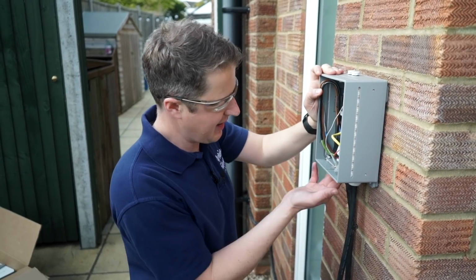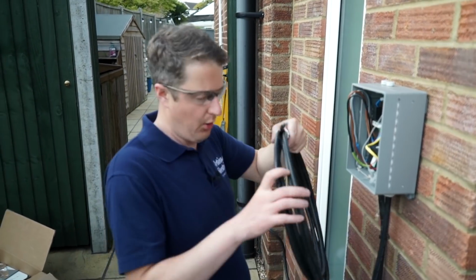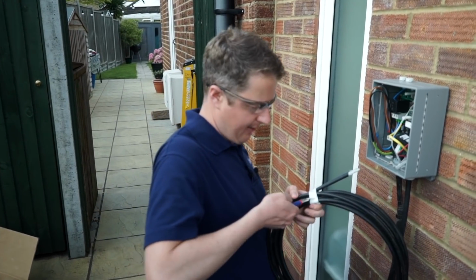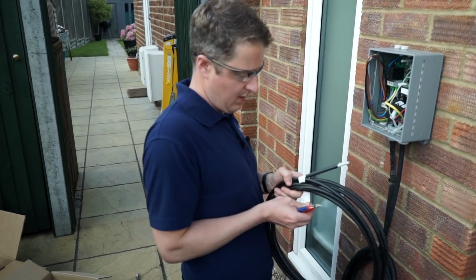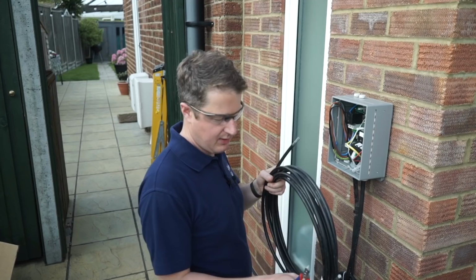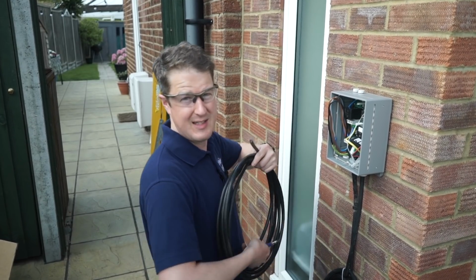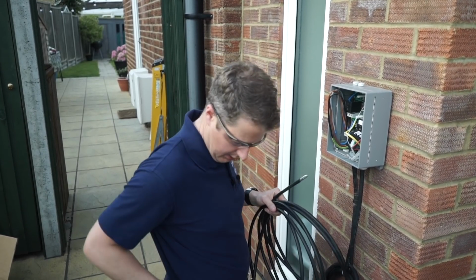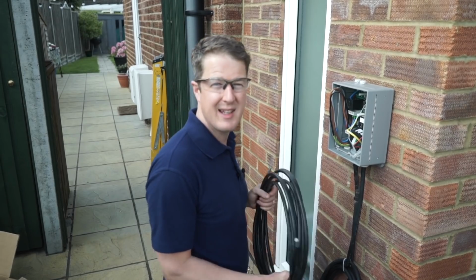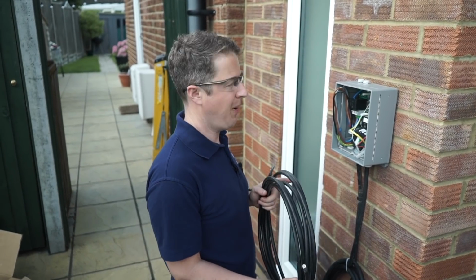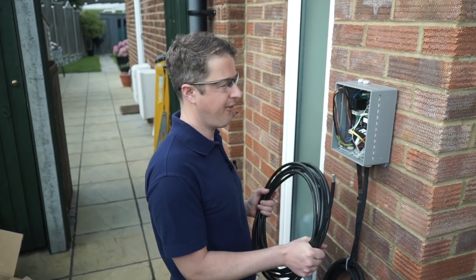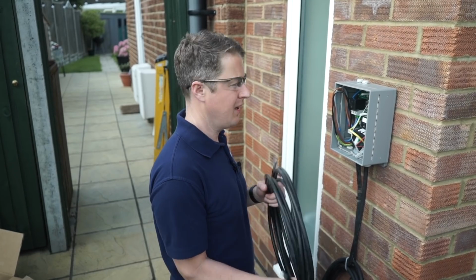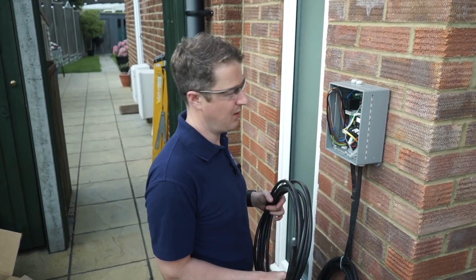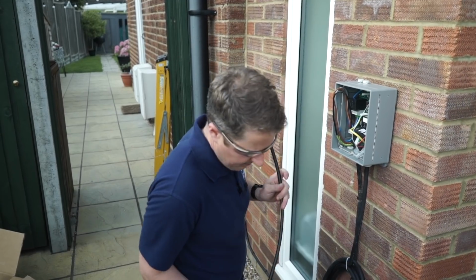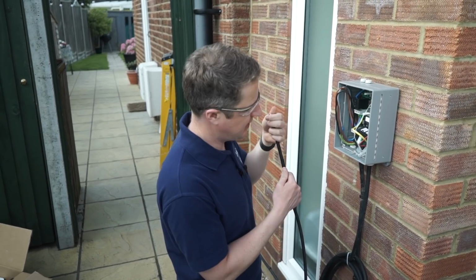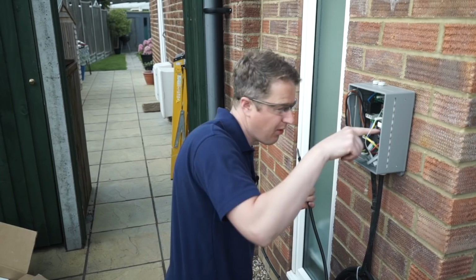Now I'm going to get the data cable in. This is armoured Cat 5e data cable, which I'm going to use to run the signal from the CTs to monitor the grid connection. We could run a hardwired data connection if we wanted to, but it's not necessary - it's got Wi-Fi, and we've got good Wi-Fi signal here, so we're just going to do the internet connection via Wi-Fi. I'm going to get this in and connect two of the twisted pairs to the CT connection, which goes here on the circuit board.